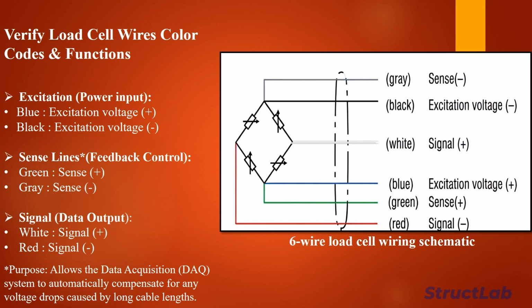Step 2. Check your load cell's wire color codes to identify their electrical functions. In this standard 6-wire configuration, blue and black handle the positive and negative excitation lines to power the bridge. Green and gray serve as the positive and negative sense lines, which let the DAQ automatically compensate for any signal loss over long cables. Finally, white and red transmit the positive and negative measurement output signals.